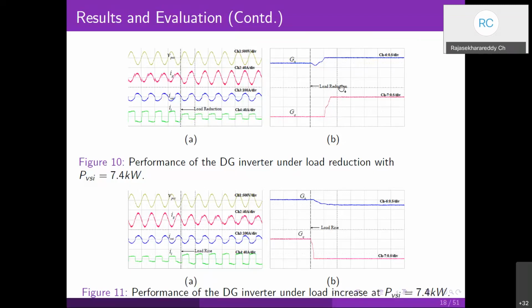Okay, you can see here the change in load happening. Then this GH value starts to change. As long as the GH value is less than 1, you can see that the GQ value is maintained at 0. Once the GH value hits 1, our control algorithm checks the inverter capacity, whether it can accommodate reactive currents or not. If yes, then accordingly it is going to change the GQ value. So that's how you can see here.